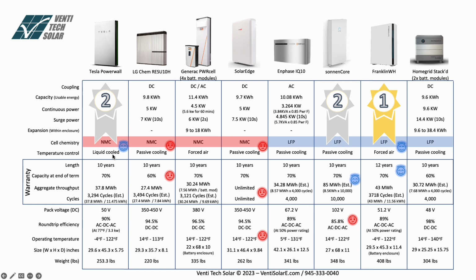On the Tesla side, if they change to an LFP technology, which I know they're working on, it will easily take the number 2 spot or even the number 1 spot if they continue to do liquid cool in an LFP product. Or in the case of Sonnen, if they would increase the round trip efficiency over here, that would be a great plus. Or if they added some active cooling, that would also take the number 2 spot easily, or even the number 1 spot. So that's all I have for now.